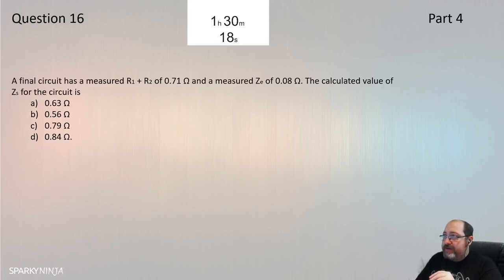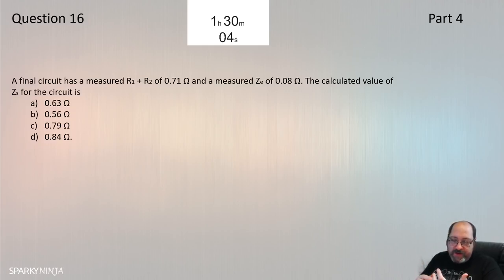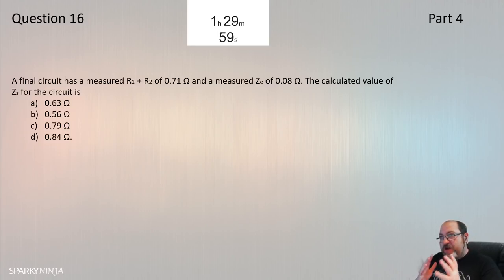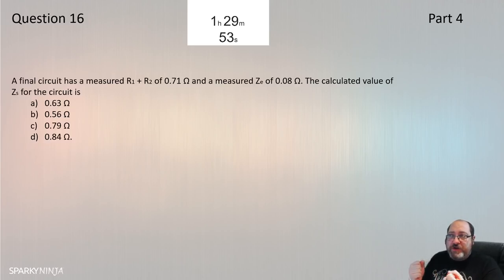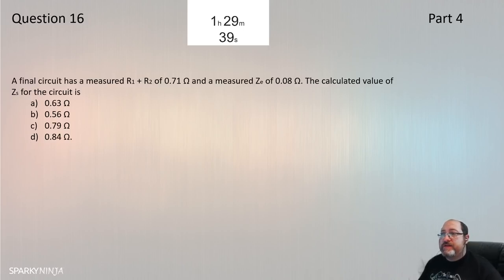Question 16: A final circuit has a measured R1+R2 of 0.71 ohms and a measured Ze of 0.08 ohms. The calculated Zs for the circuit is: Zs = Ze + (R1+R2) = 0.08 + 0.71 = 0.79 ohms. Question 16 is C — Zs equals 0.79 ohms.